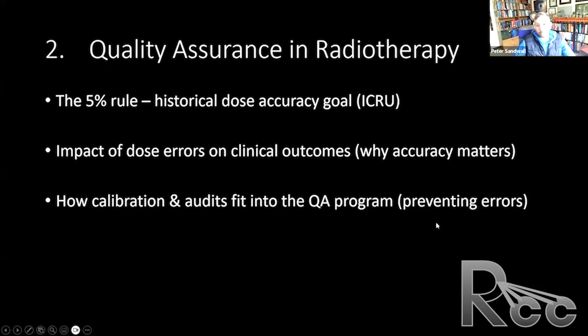So let's talk about reference dosimetry. That's what we as clinical physicists perform: we are performing dose measurements under reference conditions. I don't like the term absolute. I'm a little pedantic. This means that I'm very precise with my words. There are very few absolute dosimeters. An ion chamber is not one. Fricke dosimeters, calorimeters, and chemical dosimeters are absolute dosimeters. We do our best to calibrate them so that they're accurate, but they are referenced back to either a large free air ionization chamber or calorimetry, which is the measurement of the change in heat. So calibration of the linac output is performed using a standard ion chamber.